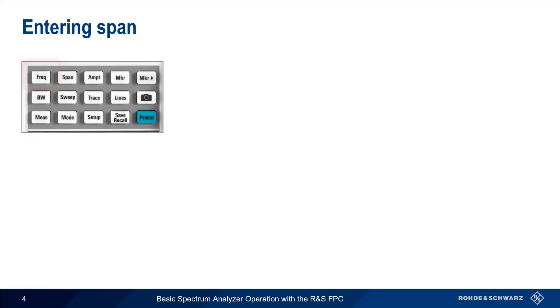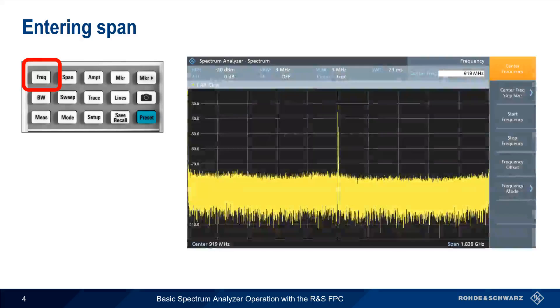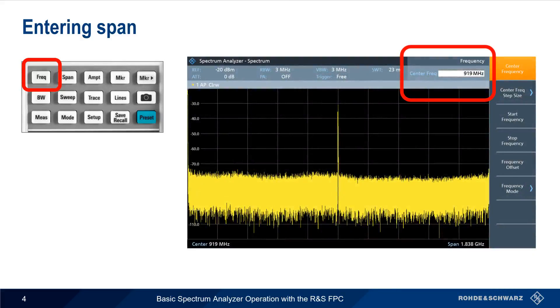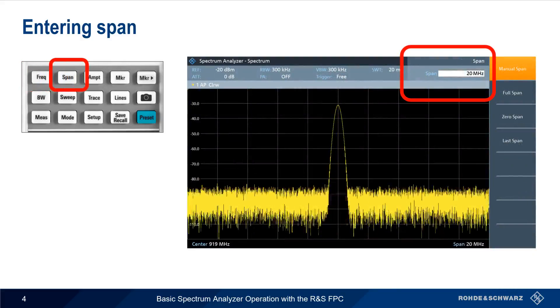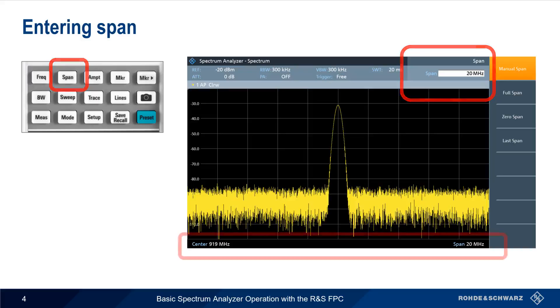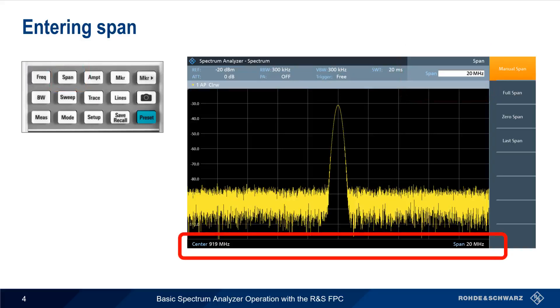The more common way to enter a frequency range is using center and span. We use the frequency hard key to enter our center frequency, in this case 919 MHz, and then use the span hard key to enter our span, here 20 MHz. As before, our center and span are displayed below the trace.